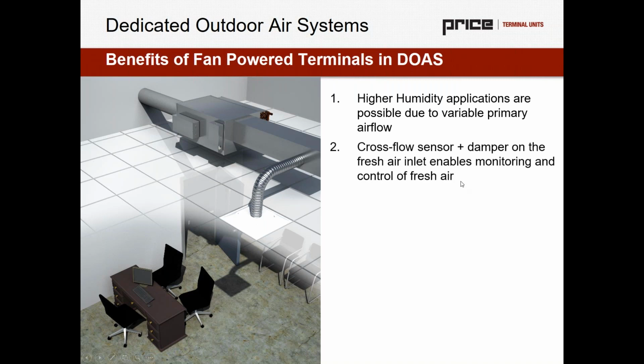So that crossflow sensor and damper also enables the monitoring and control of fresh air for demand control ventilation type systems. So providing only the amount of outdoor air that the system needs based off of zone measurements, whether it's occupant counting or carbon dioxide monitoring. The fact that we have this local fan is super excellent because it allows for morning warm up and night setback. So if we have an unoccupied mode through the night, we can actually turn our rooftop unit off, which is going to allow for significant energy savings, and we can still heat up the space and get it ready for occupation without having to turn on that rooftop unit.